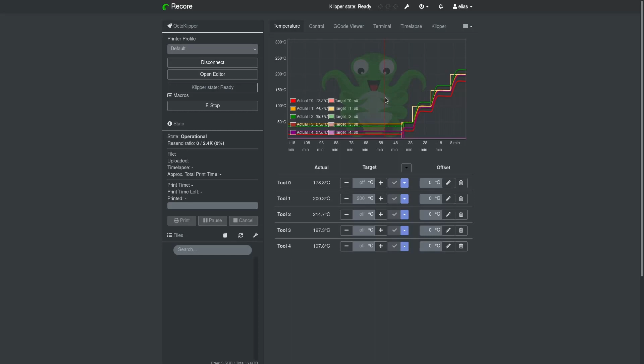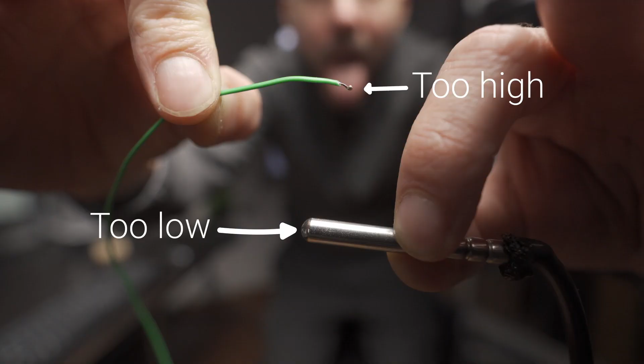I can now measure the temperature of all the different sensors on Recore and compare them with the reference. At room temperature, 3 sensors are off. If I measure the temperature at different levels, I can see that the Thermistor is pretty close to the reference at 200 degrees. But the thermocouple is still too high and the PT1000 is still too low. Let's start by fixing the thermocouple.